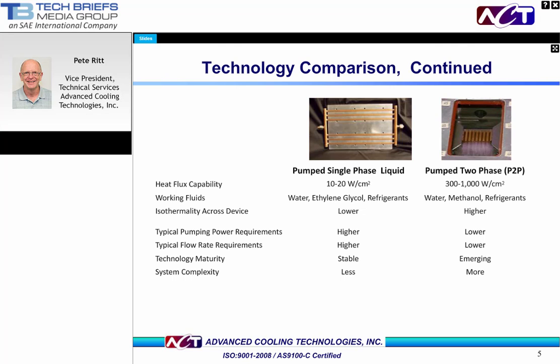Single-phase pump liquid systems have a variety of potential working fluid selections, including water, ethylene glycol, combinations of water and ethylene glycol, and refrigerants. Pump two-phase systems, which are closed and pressurized, are usually refrigerant-based, but can be used with water, methanol, or combined water-methanol systems. A real advantage for weight and space-confined application is the significantly reduced pumping power and flow rate requirements for pump two-phase versus pump liquid systems. We'll put some numbers to that on the next page.